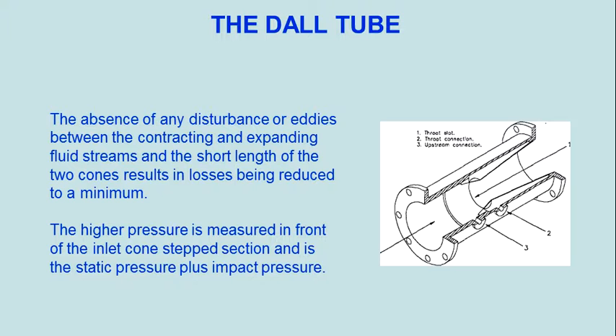The absence of any disturbance or eddies between the contracting and expanding fluid streams and the short length of the two cones results in losses being reduced to a minimum. The higher pressure is measured in front of the inlet cone step section and is the static pressure plus impact pressure.